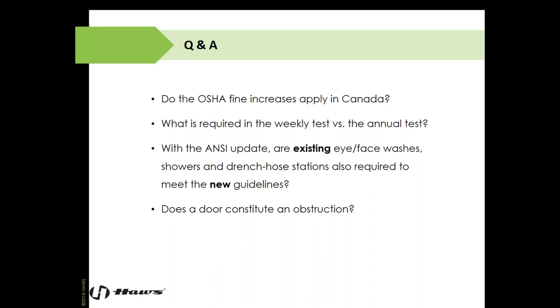Another important note is portable type equipment, self-contained equipment. No activation is required on self-contained equipment. All that you need to do is approach the equipment, open it up, make sure that there's enough flushing fluid for your full 15 minutes, based on the manufacturer's suggestions and requirements. And that's pretty much it. You just need to make sure there's enough water in there for a 15-minute flush and that there's no growth or anything like that in the water, and you're good to go.